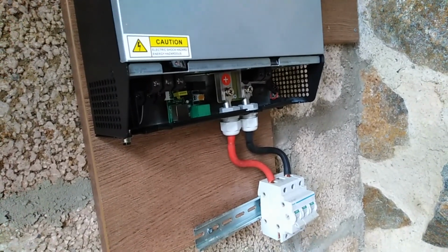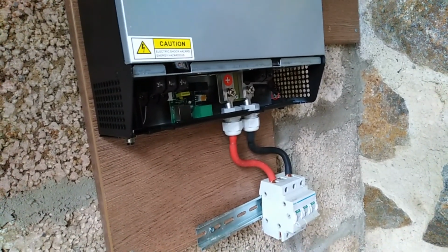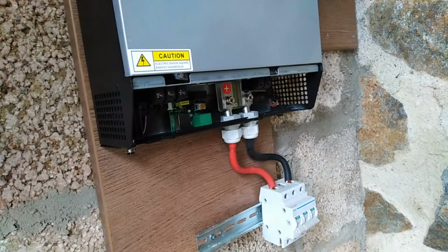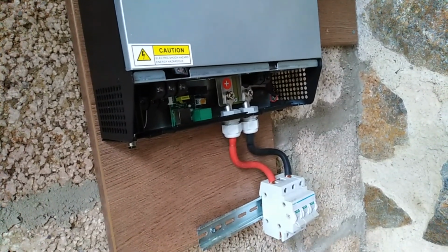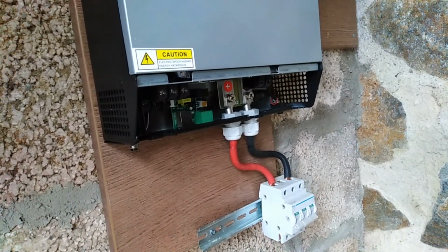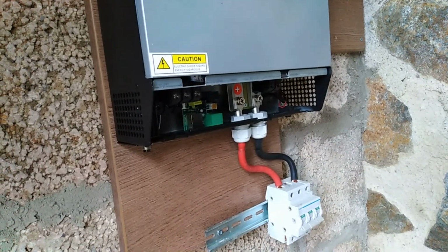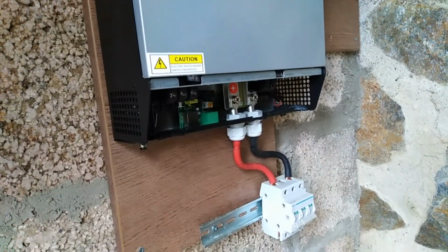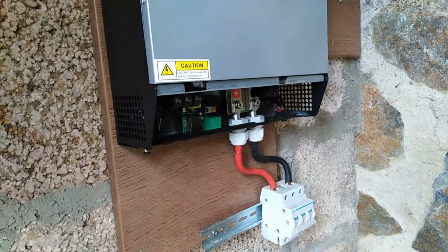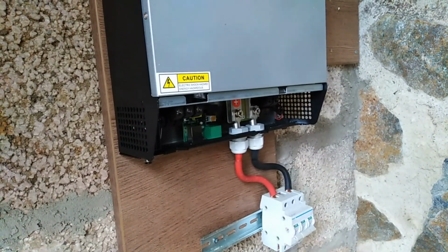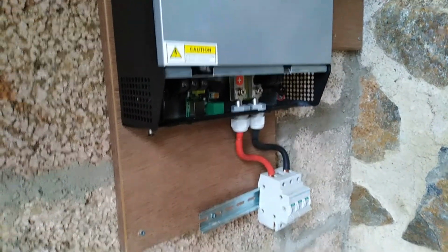I have to do the same for the solar panel connections to a circuit breaker, and then connect two mains leads, one mains in, one mains out. Then all I've got to do is the long black and white and red leads on the floor, connected to the bottom of that circuit breaker and connected to the batteries, and then switch it on.